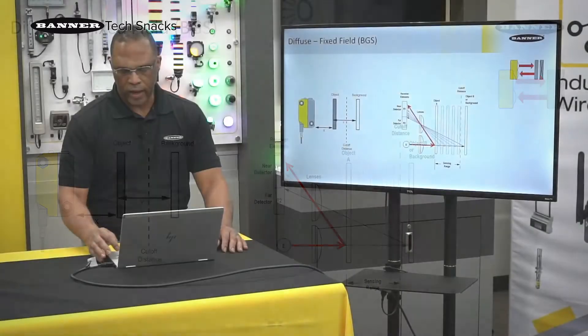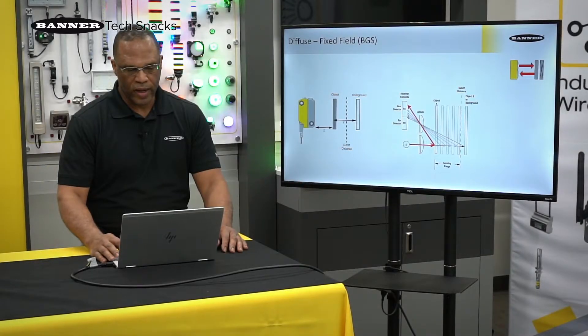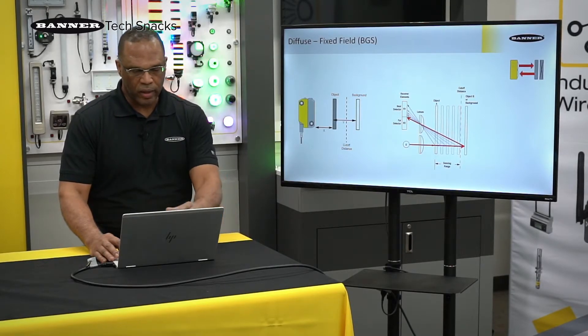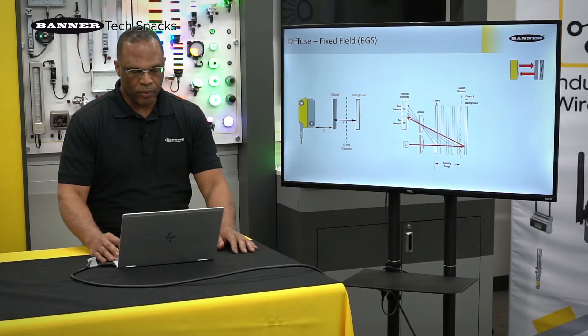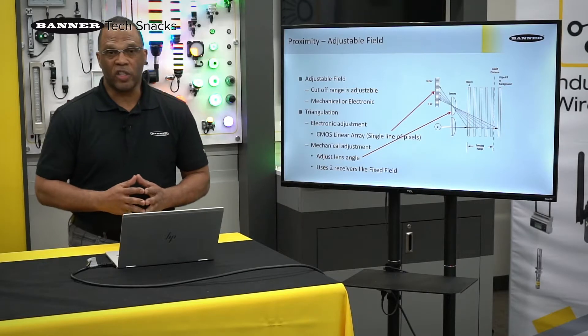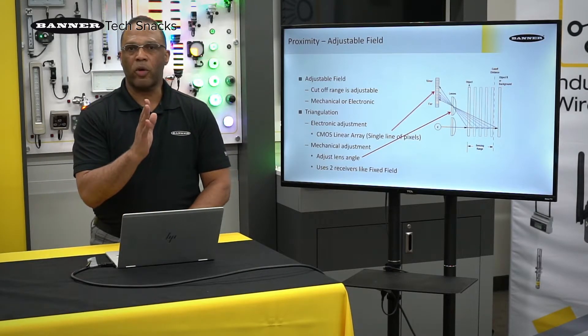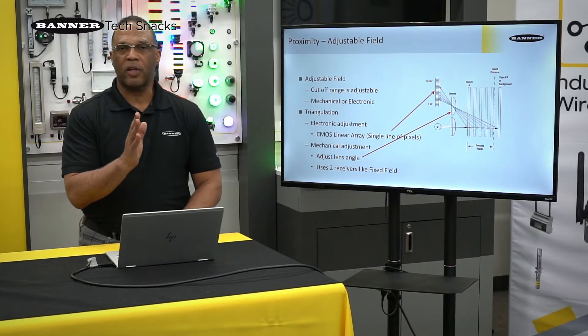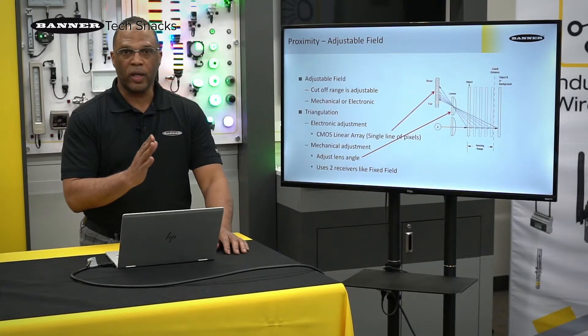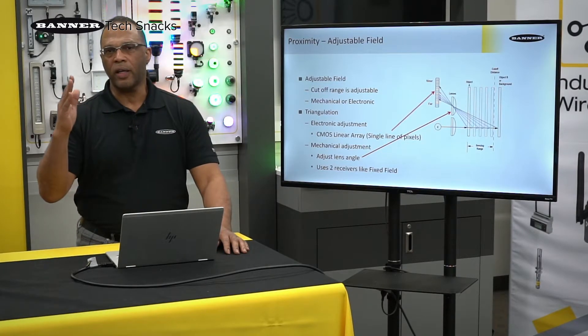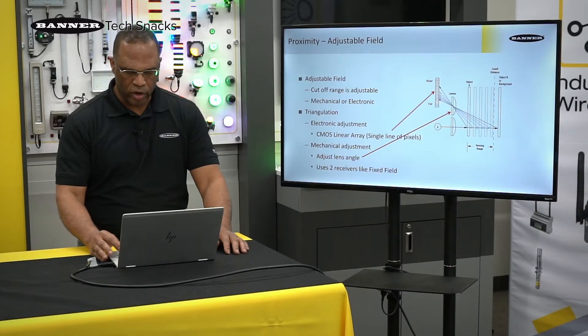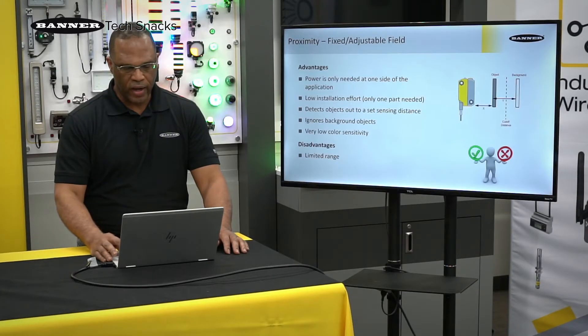You can have a shiny bracket behind a target and a fixed field sensor will ignore that — it's a huge advantage. We also have adjustable field, where the range is no longer fixed. It's adjustable, so you can dial it in to the range that you need and continue to get background suppression. Another great advantage.